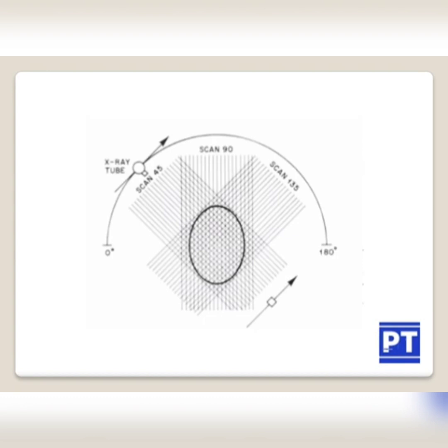You can understand from the figure that the gantry moved through two different types of motion — one linear and the other rotatory, that is, translate-rotate. The linear motion was repeated 180 times. Between each of these 180 linear movements, the gantry rotated 1 degree. The gantry rotated from 0 to 1 degree each time, so the total rotatory motion encompassed a 180-degree semi-circle. The axis of rotation passed through the center of the patient's head.